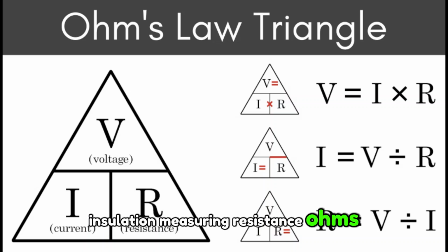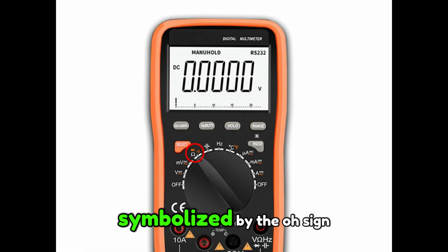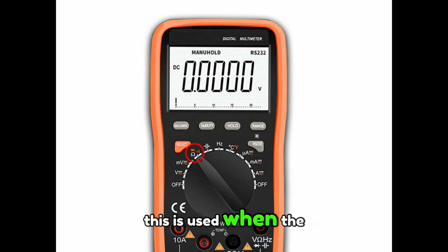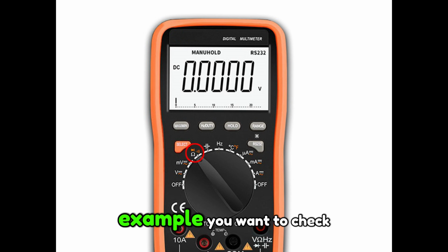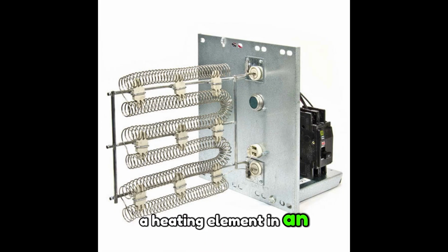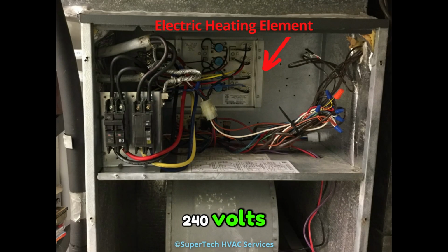Measuring resistance, ohms. Set your meter to ohms, symbolized by the omega sign. This is used when the power is off, and you want to test the integrity of a component. Example, you want to check a heating element in an air handler. The nameplate says 7,000 watts, 240 volts. Use R equals V squared divided by P, which is 240 squared divided by 7,000, equals 8.23 ohms.